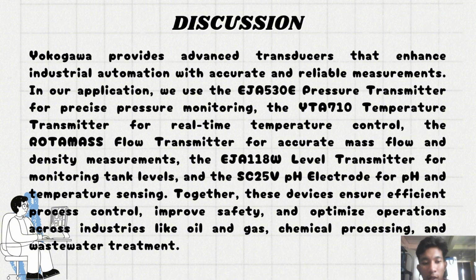After all, we have discussed the application, installation, and the background of Yokogawa. We can see that Yokogawa provides advanced transducers that enhance industrial automation with accurate and reliable measurement. In our application, we use the EJA 530E pressure transmitter for precise pressure monitoring, the YTA 710 temperature transmitter for real-time temperature control, the Rotamass flow transmitter for accurate mass flow and density measurement, the EJA 118W level transmitter for monitoring tank level, and the SC25V pH electrode for pH and temperature sensing. Together, these devices ensure efficient process control, improve safety and optimize operations across industries like oil and gas, chemical processing and wastewater treatment.